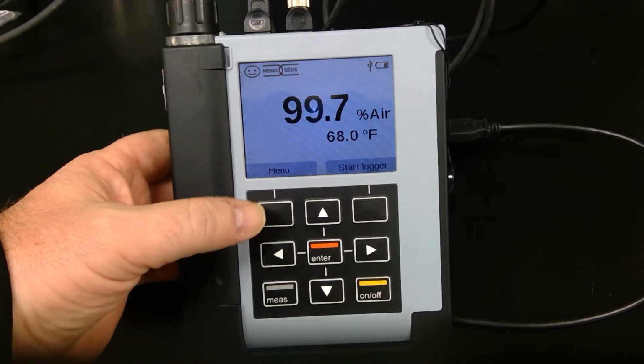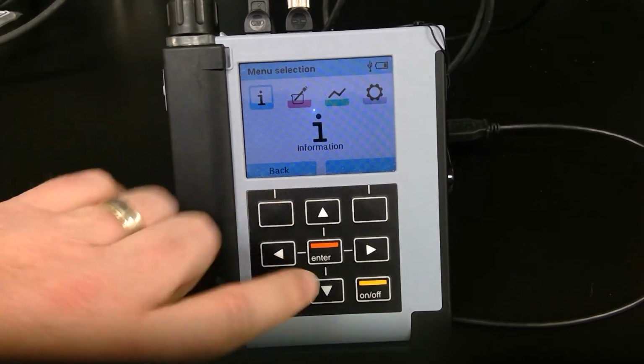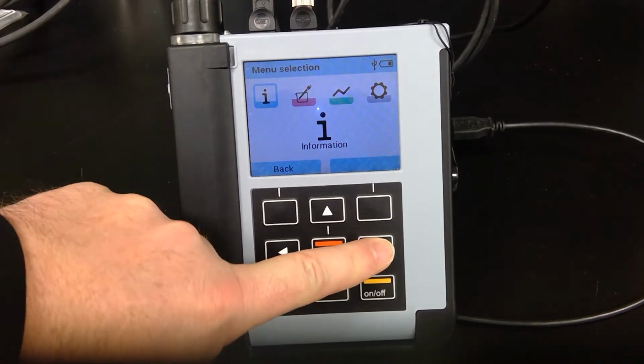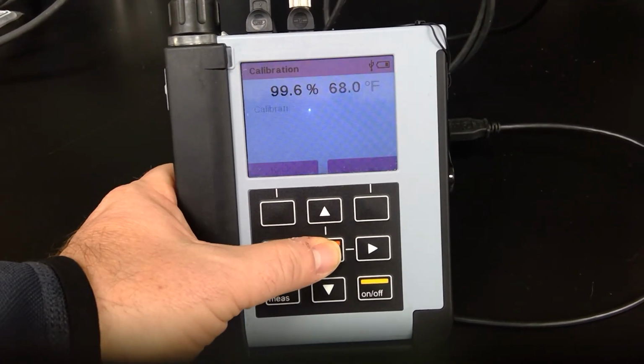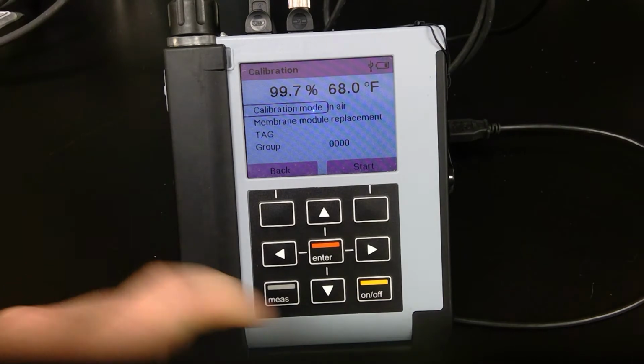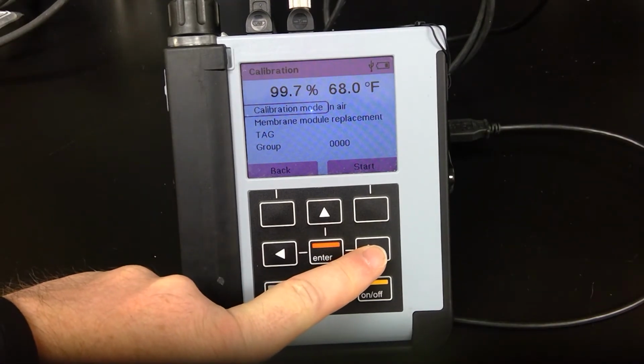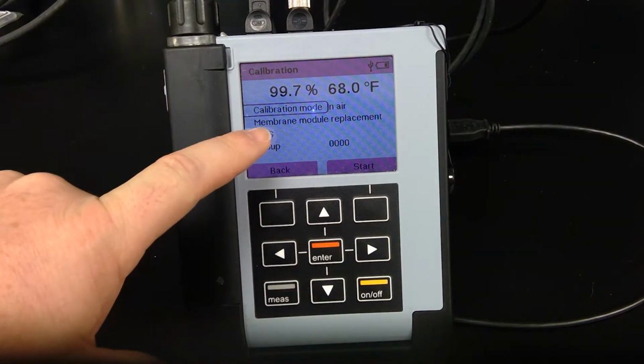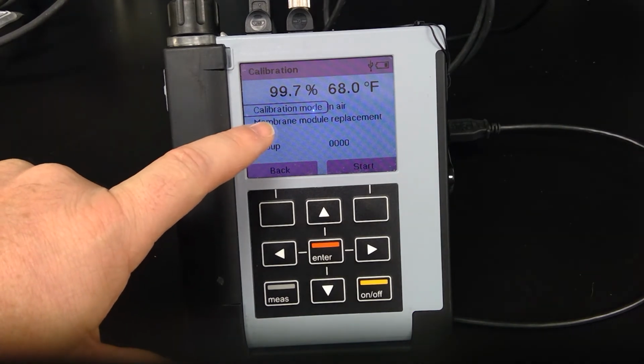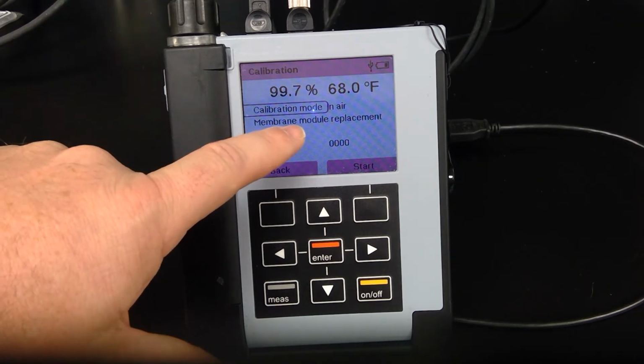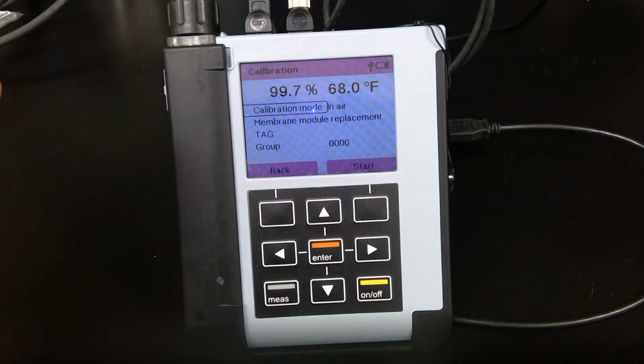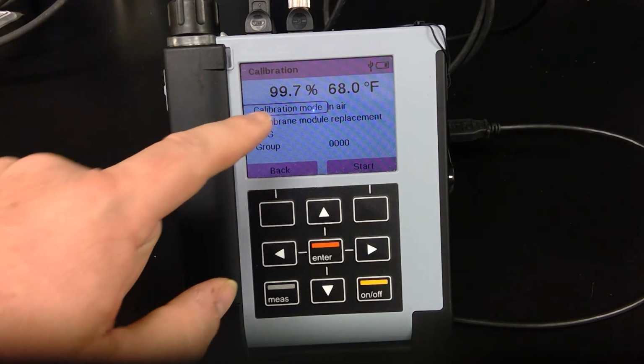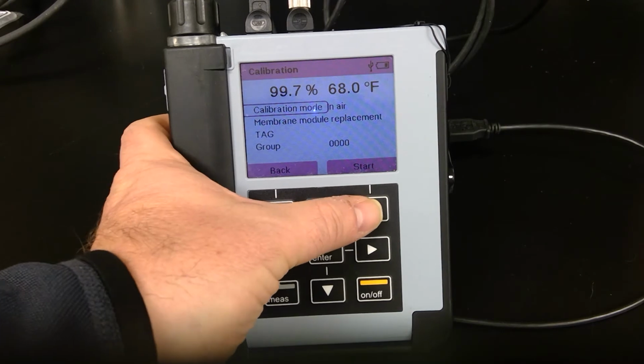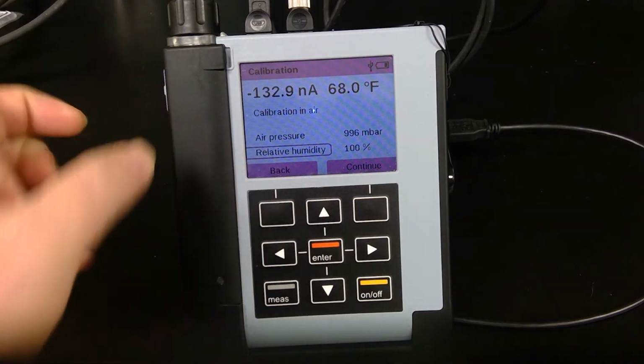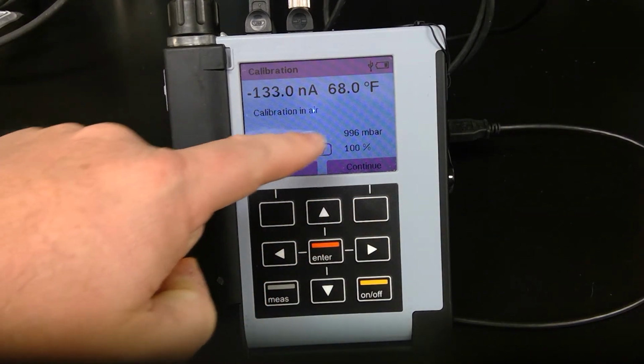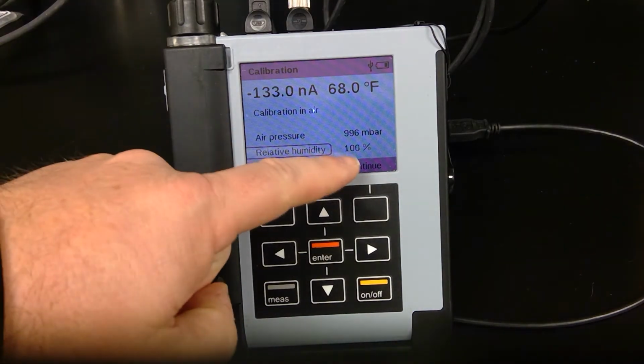So what we're going to do is go into menu, go over to calibration, hit enter, and then go into air calibration. All right, now if you recall, in the previous video when we did the membrane module replacement, that's already completed. We don't have to do that again. So calibration mode in air, I hit start. And as you can see, it's giving me my air pressure at 996 millibar and 100% humidity.